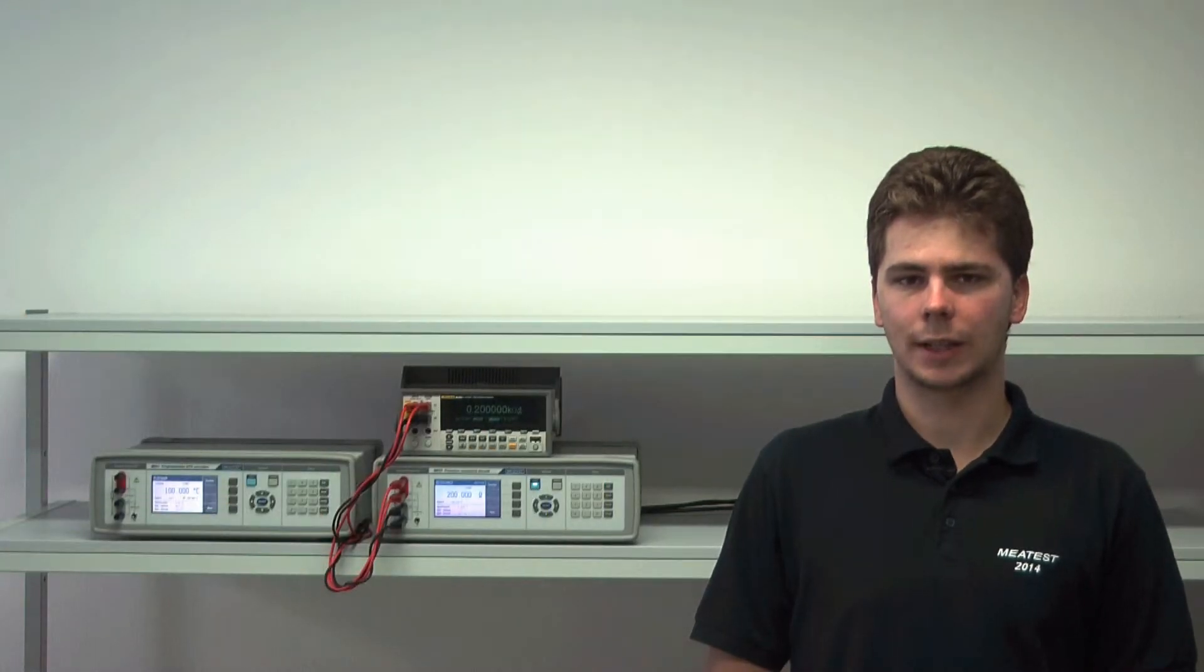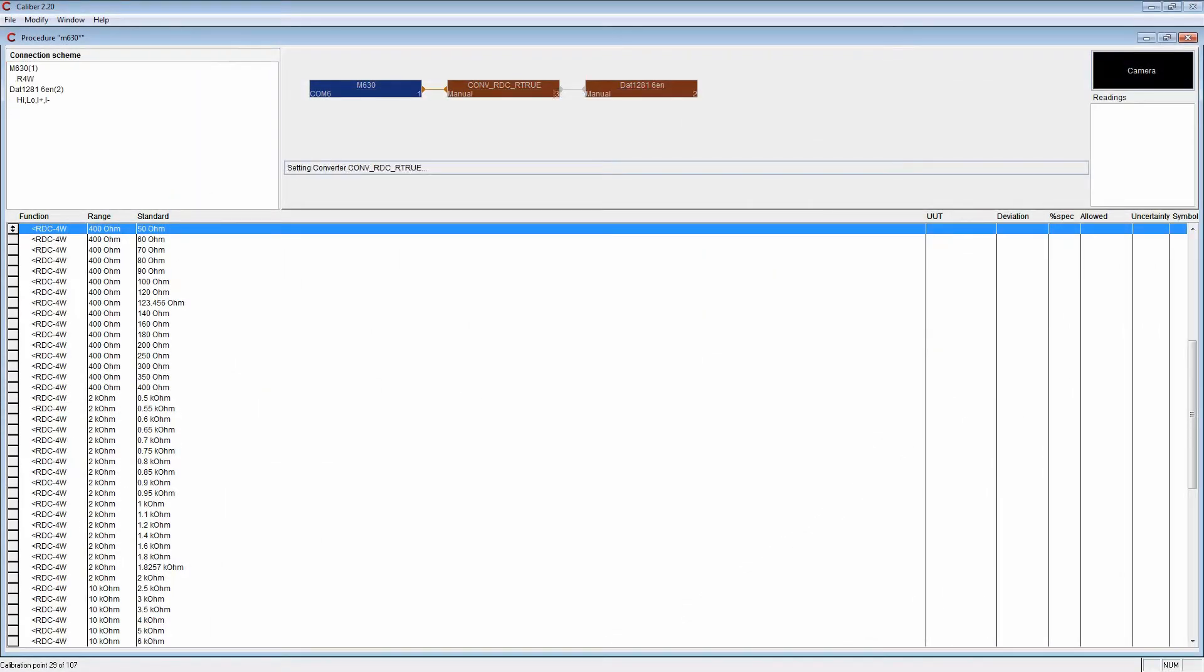To get the most out of your Meatest decade, use Calibre, a software for fully automated calibration. Using Calibre, you can simply create your own calibration procedures, execute them and export the calibration data for further processing.